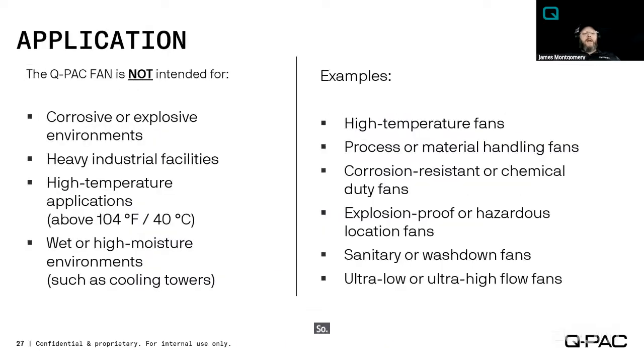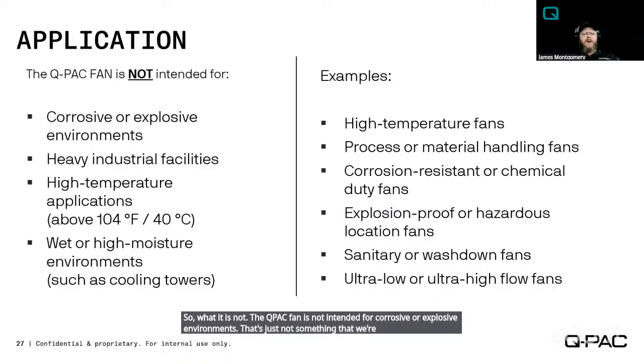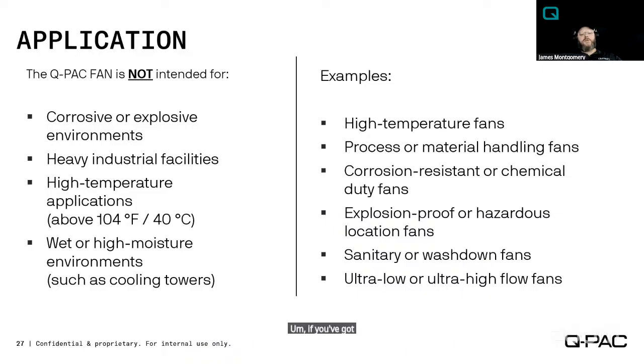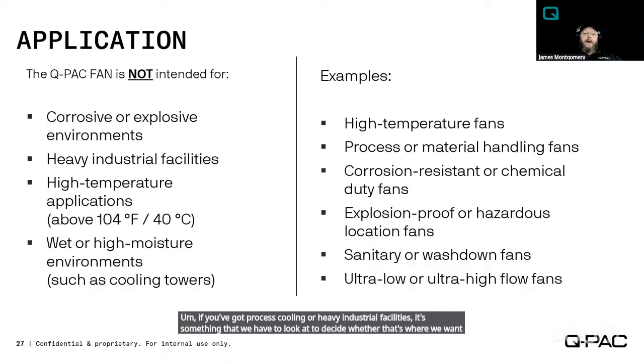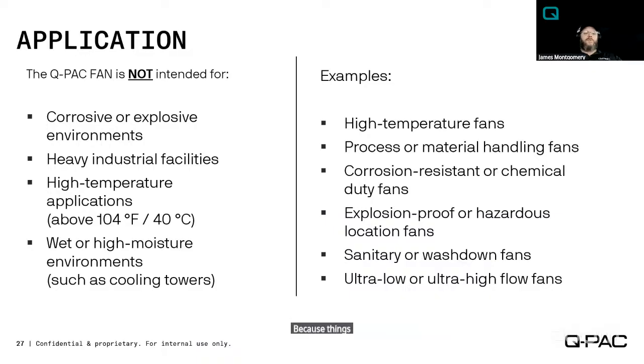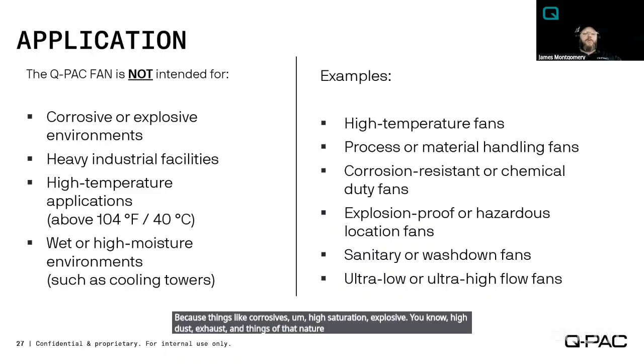So, what it is not. The Q-PAC fan is not intended for corrosive or explosive environments. That's just not something that we're doing. Also, heavy industrial facilities kind of fall under that same realm. If you've got process cooling or heavy industrial facilities, it's something that we have to look at to decide whether that's where we want to work, because things like corrosives, high saturation, explosive, high dust, exhaust, and things of that nature may not be compatible with our system.